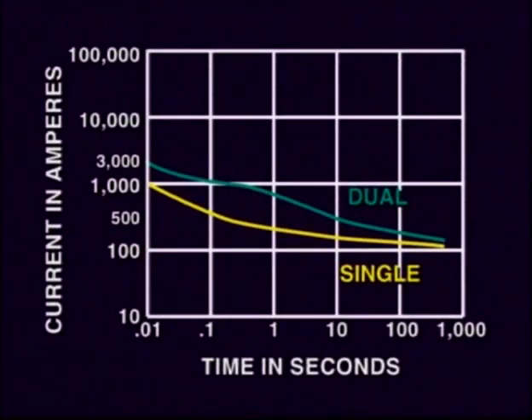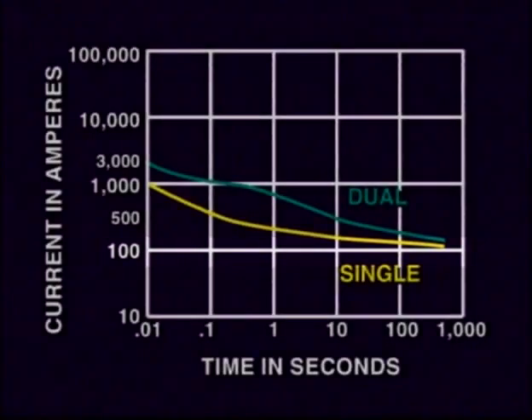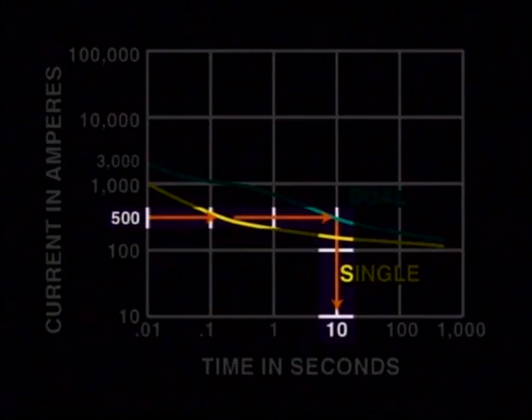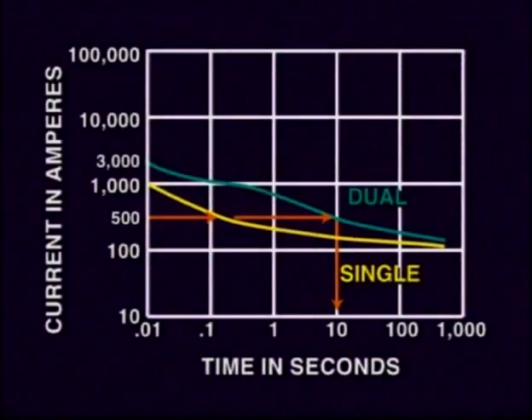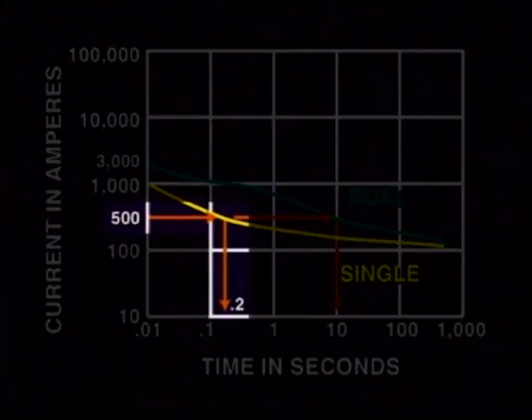As this graph describes a single-element and dual-element time delay fuse, rated at 100 amps, it will take 10 seconds for the time delay to open at a current of 500 amps, whereas it will take 2/10 of a second for the non-delay fast-acting fuse.